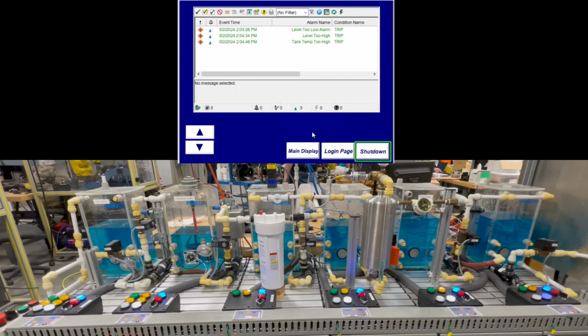Then going down to the alarm history page, I'm just going to press the E-stop so you can see that alarm show up, and then the process will all stop at once. And you can see that alarm show up and start blinking in my alarm history page.